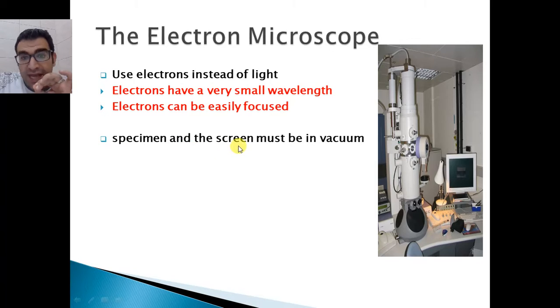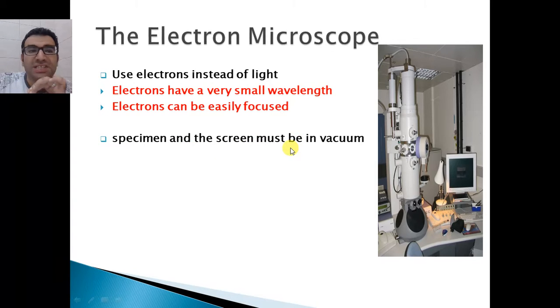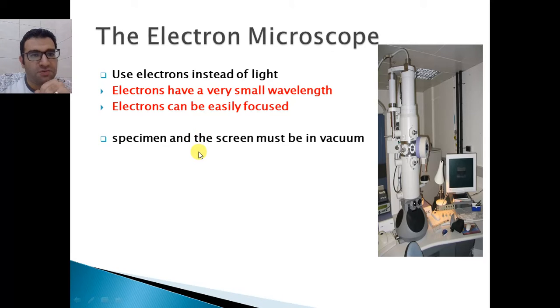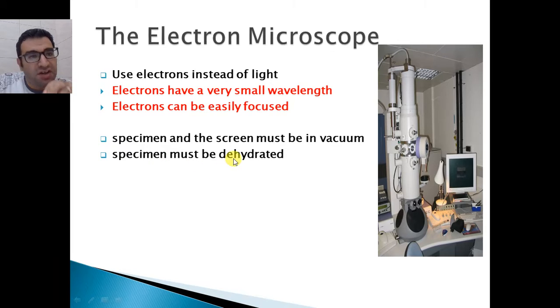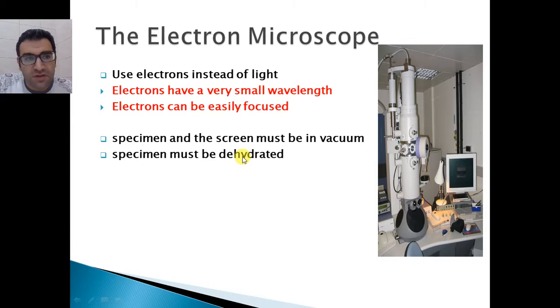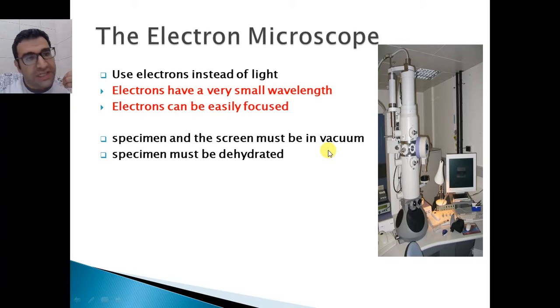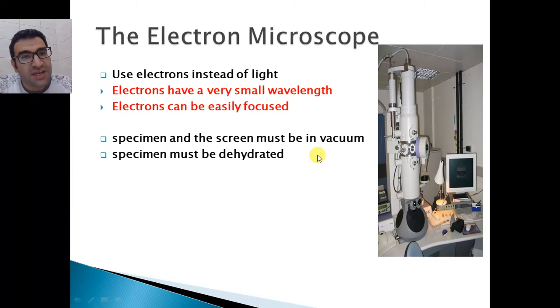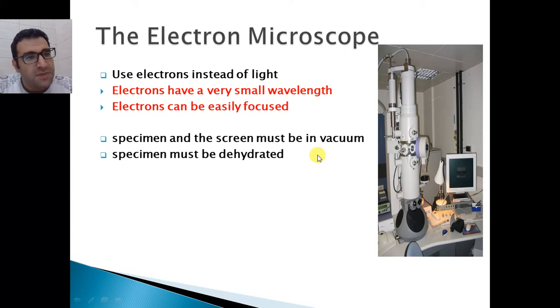However, the specimen and the screen must be in vacuum. The reason is that vacuum means no air — if there was air, the air particles could distract the electrons. One more requirement is that the specimen must be dehydrated, meaning without any water. The reason is that at vacuum, water will boil even at room temperature without needing 100 degrees Celsius. So we must make sure that the specimen used in an electron microscope is completely free of any water particles.